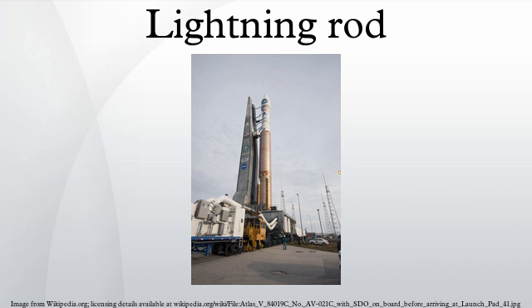However, high-speed photography has clearly demonstrated that lightning is actually composed of both a cloud component and an oppositely charged ground component. During cloud-to-ground lightning, these oppositely charged components usually meet somewhere in the atmosphere well above the Earth to equalize previously unbalanced charges. The heat generated as this electrical current flows through flammable materials is the hazard which lightning protection systems attempt to mitigate by providing a low-resistance path for the lightning current. No lightning protection system can be relied upon to contain, or control lightning completely, but they do seem to help immensely on most occasions of lightning strikes.